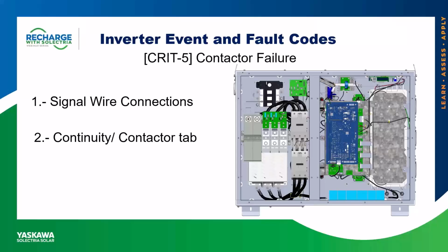Now that the inverter is in a safe state, they can manually, with a screwdriver or something, push in the contactor tab and then test continuity on each phase, top and bottom. If it rings out, you know the contactor is good, and it may be related to the signal voltage they're getting. This is going to lead us to our last and final step, which is signal voltage testing.